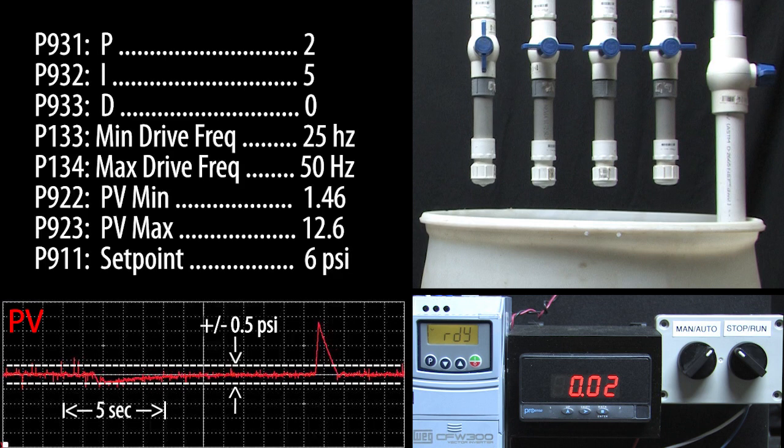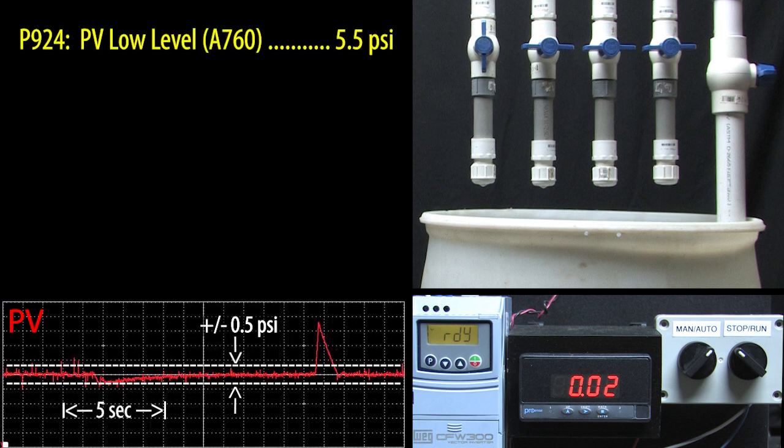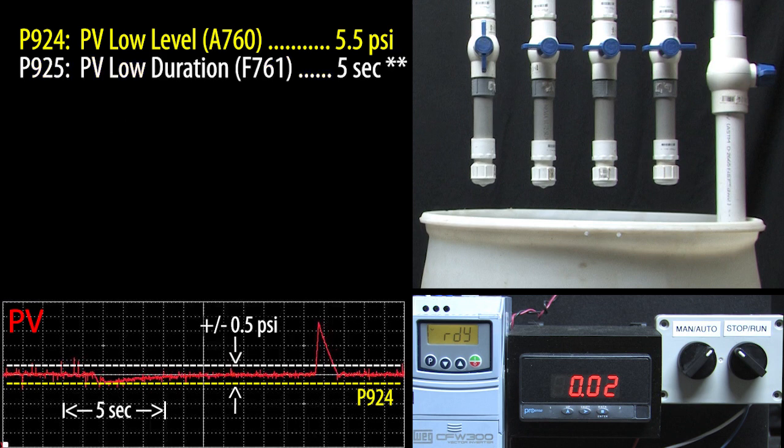These are the key parameters I've set up, which is basically what we did in the quick start video except I increased the P gain to make sure the system ramps up within that 5 second window. Parameter 924 is the low level alarm. That will be 5.5 PSI. Notice that this is in the engineering units that we specified in parameters 922 and 923. Parameter 925 is the duration of the condition that will generate a fault. We want that to be 5 seconds.